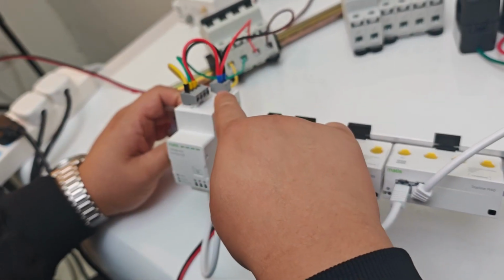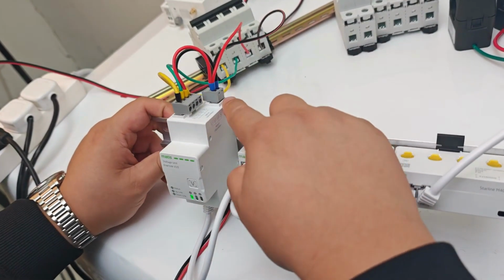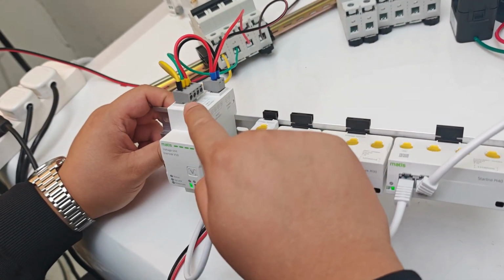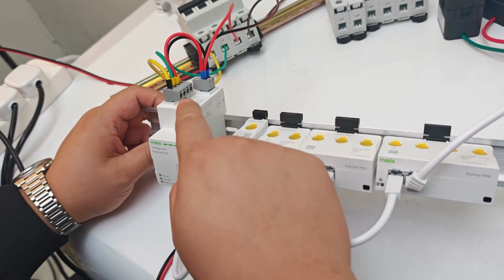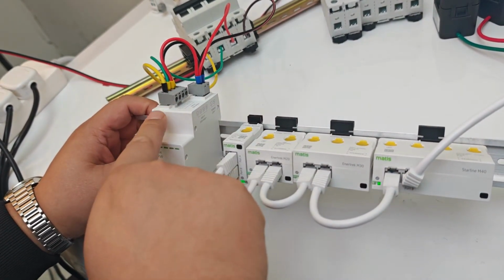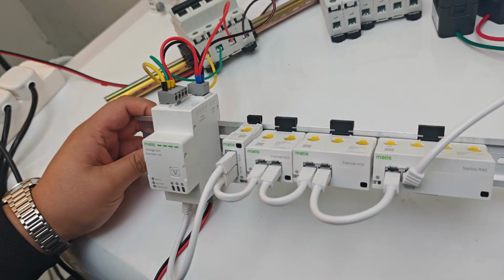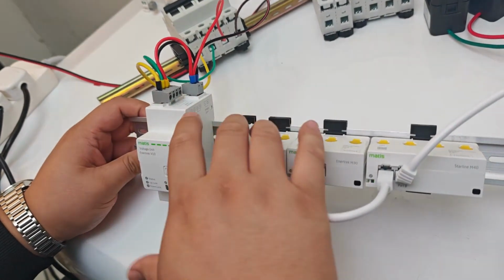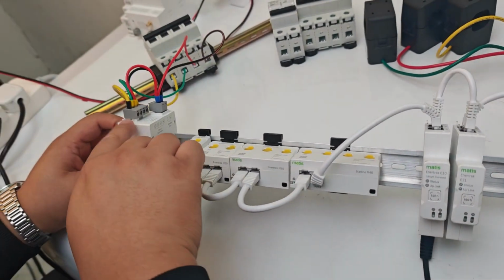At the top of our voltage module, there are two ports, one for power supply and one for voltage sampling. When wiring, you must connect the voltage sampling port of the voltage sampling module. This is because this port provides the metering voltage reference for the subsequent submodules.